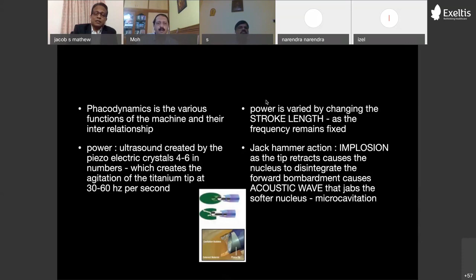As the tip retracts, a negative pressure is created. Water rushes in, moving at a very fast pace, so an implosion occurs, and as the tip moves forward, it causes a bombardment. It's like a hit there, and that causes an acoustic wave also. So basically, it works on the principle called microcavitation, where the nucleus at the tip of the probe gets broken down because of this agitation, pulverized into small pieces. Till the third generation, we used to have longitudinal phaco, where the tip moves to and fro in the longitudinal axis.